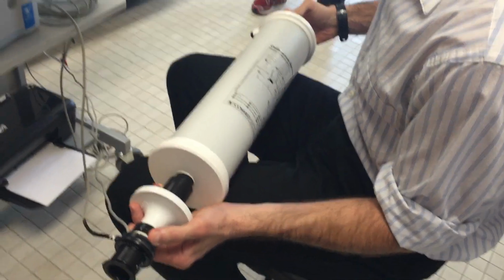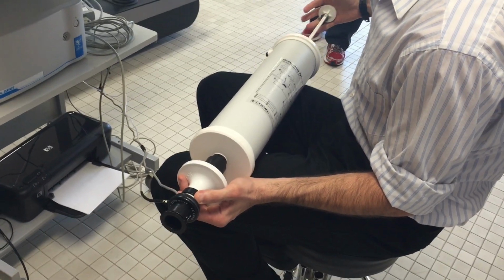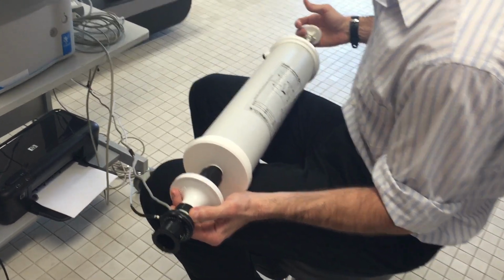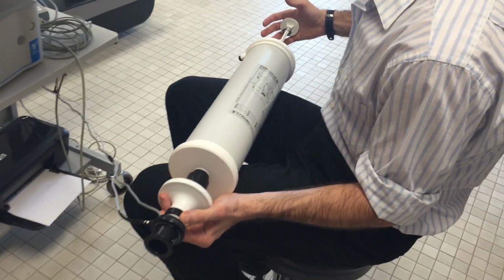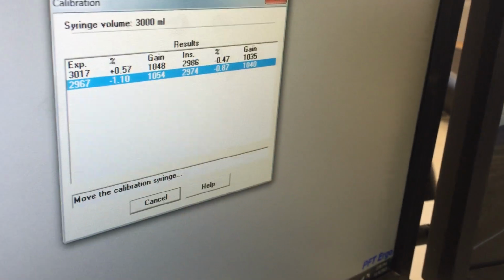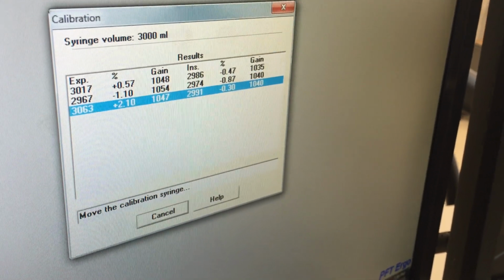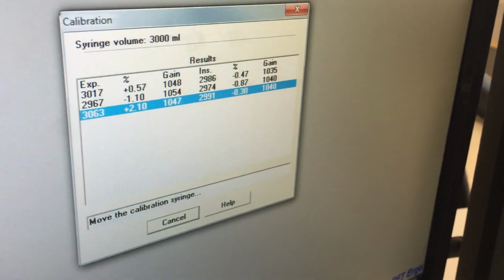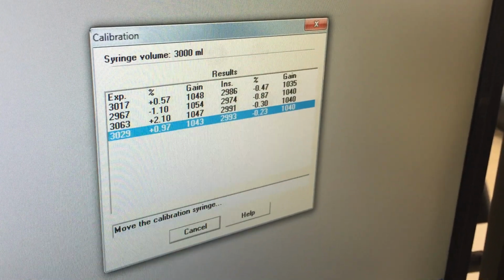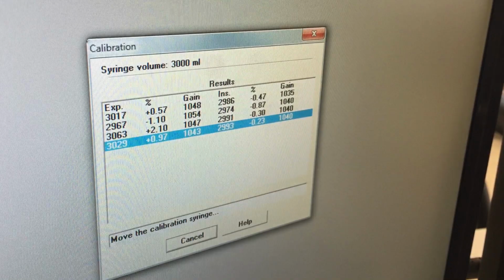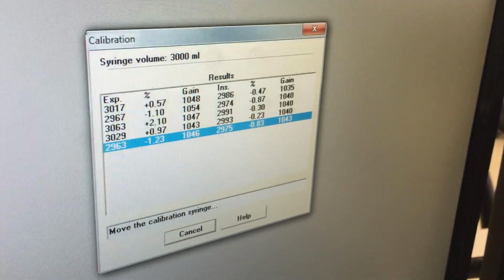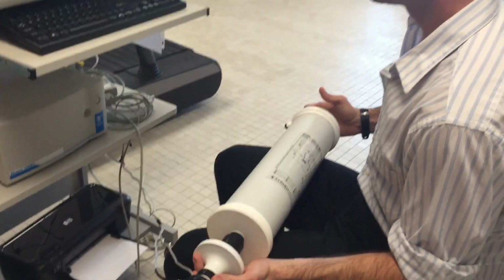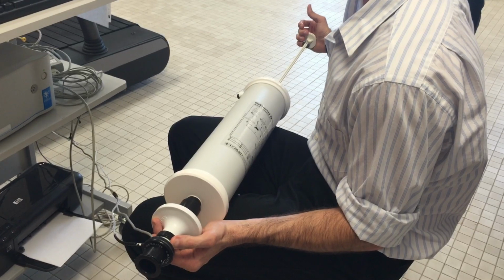What we're looking for is the gain. So number 1, we're going to get situated, and then we're going to use the syringe like so. We want nice, smooth strokes, because if we look at the computer screen, on the right-hand side, you'll see the gain, 1035, 1040. And what we're doing is we're trying to make sure that every time we're getting as close as possible to that number. So if you watch the syringe here, you can see that every time I'm trying to stay nice and controlled, trying to keep the numbers as close as possible.